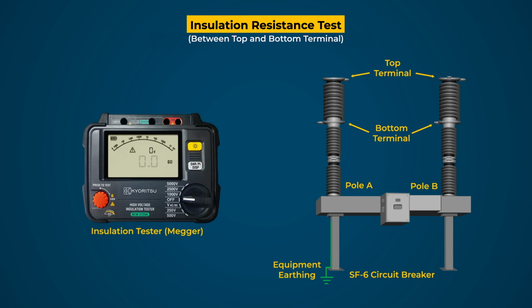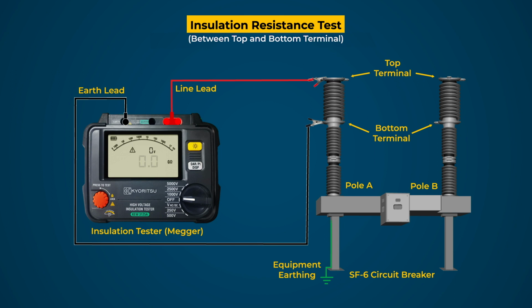Now connect the lead of the line terminal of the tester to the top terminal and the lead of the earth terminal of the tester to the bottom terminal of pole A. After that, check all the connections and select the DC voltage level to 5 kV in the test kit. Now, press the test button.